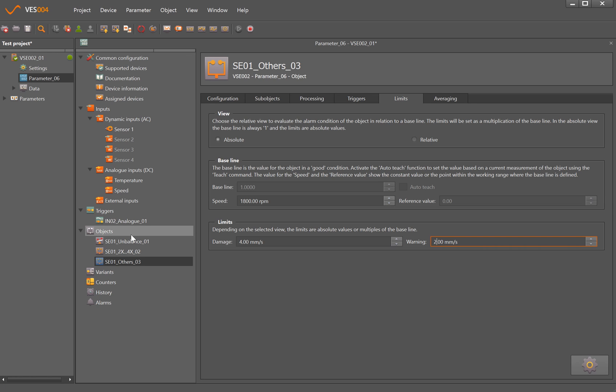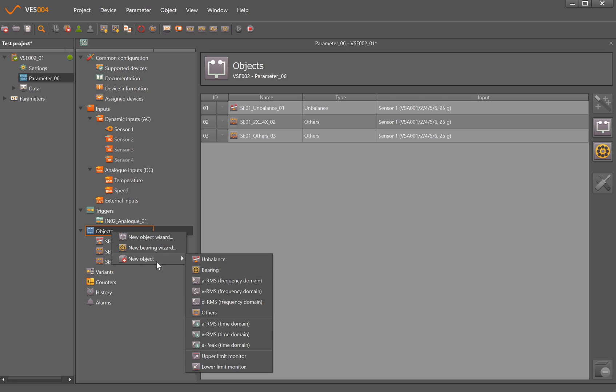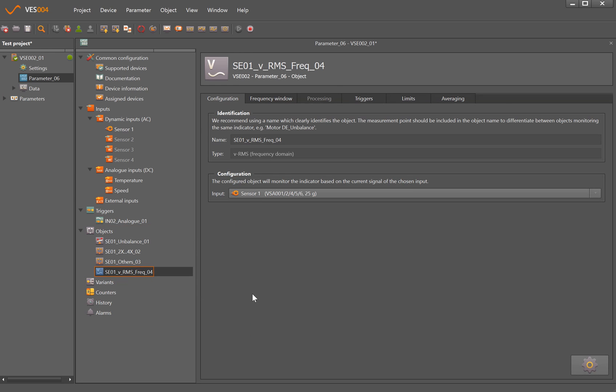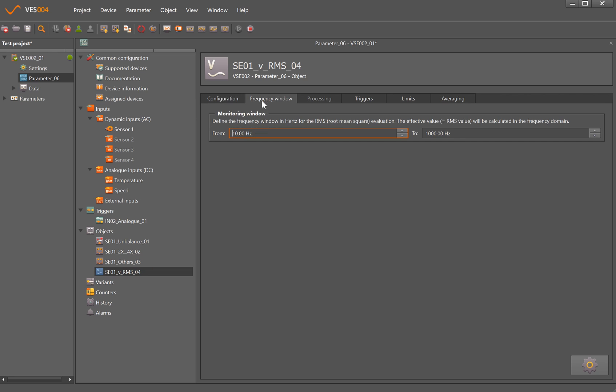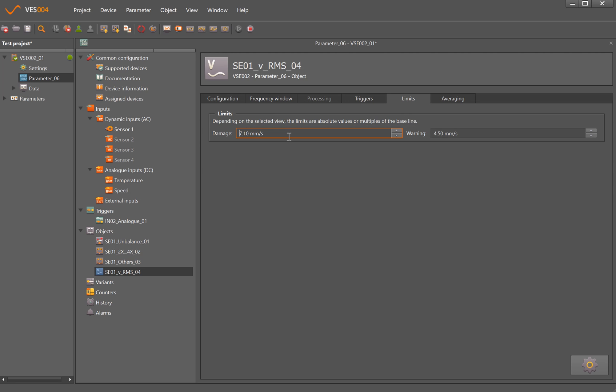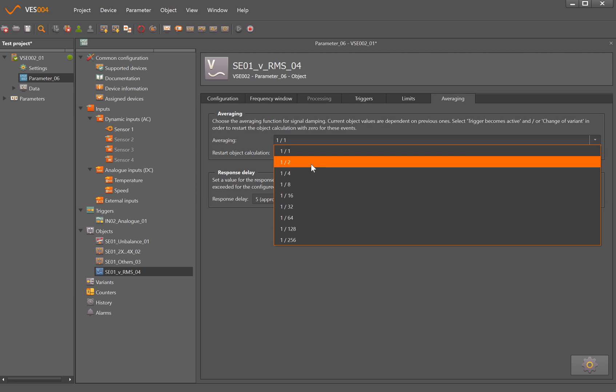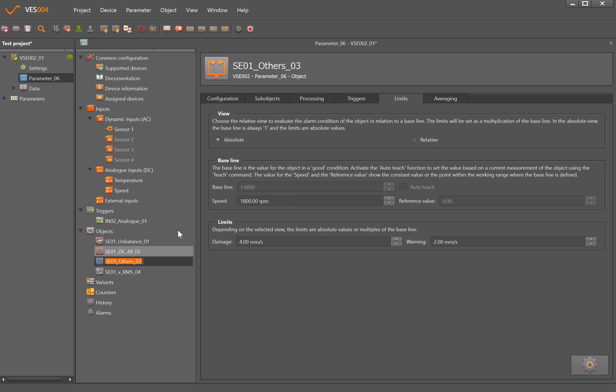The next parameter we will set up is just to the ISO 10816 standard, so we can set up rms velocity. We can do that in either the frequency or the time domain, doesn't make a great deal of difference, so I'm just going to do frequency domain. And if I change just for neatness change that to there, and the default for that is ten to a thousand hertz. And there's no trigger here because that's just looking at ten to a thousand hertz regardless of the speed. And it puts in some levels based on the ISO standards. And again we can change the averaging if we like. So I'm just going to go back to this third one here and rename it just so it means a bit more rather than others. So if I change that to 2x to 10x.